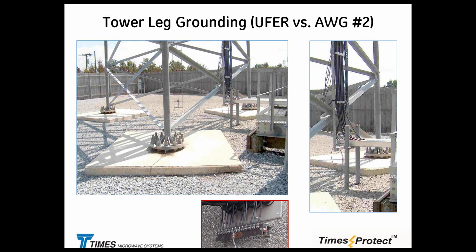So here is one a bit of a nonsense right here, but we always do it this way, right? We put a ring around each tower leg, 3 grounding rods, and that step potential rise is going to be sitting right here at the tower leg, instead of taking nice radials and running this from each leg, you know, away.